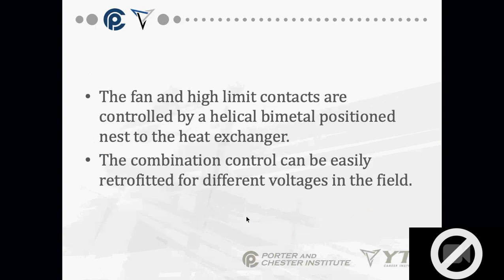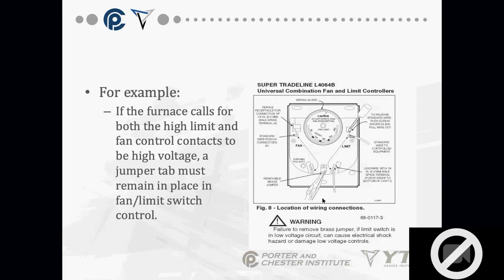The fan and high limit contacts are controlled by a helical bimetal positioned next to the heat exchanger. The combination control can be easily retrofitted for the different voltages in the field. Okay, it's very easy to change the voltage requirements. You just cut a little metal tab inside of it. This diagram over here shows someone with a pair of pliers breaking the metal tab. If I break the metal tab, I can have one side high voltage, one side low voltage, or two different circuits.